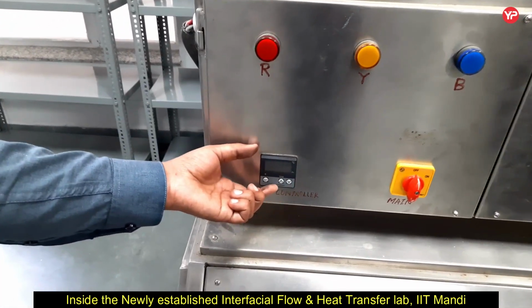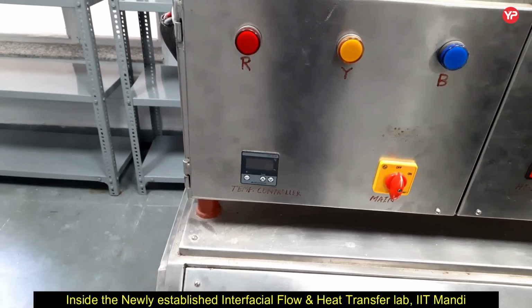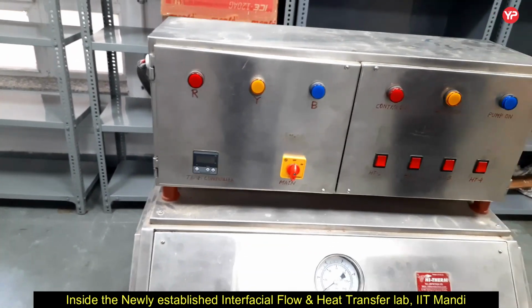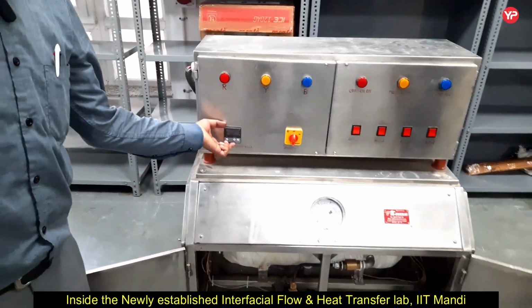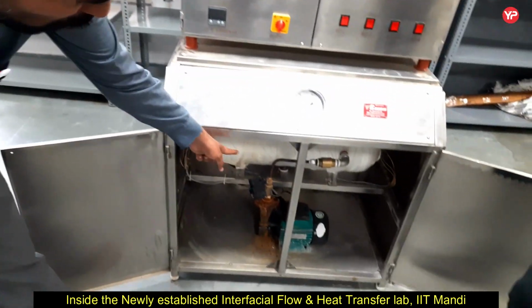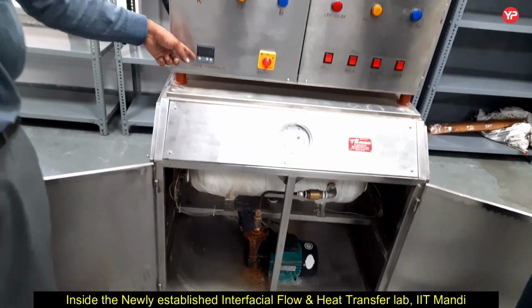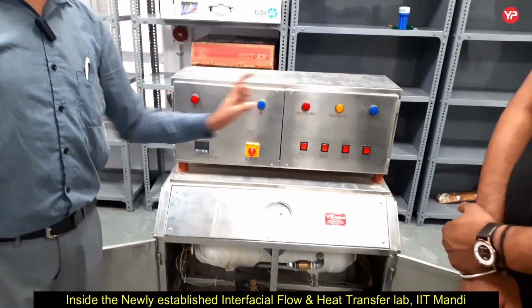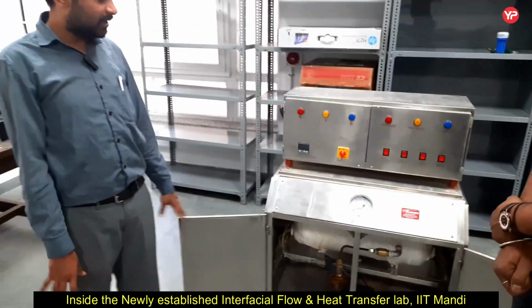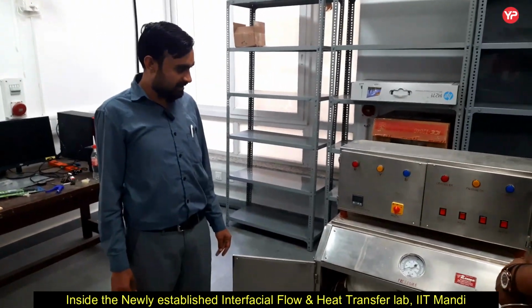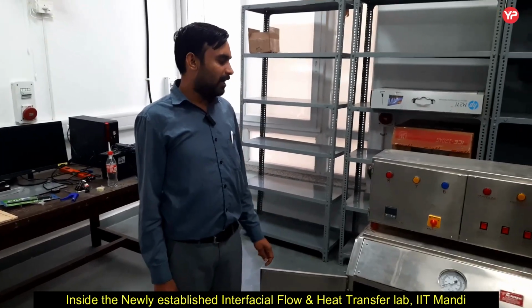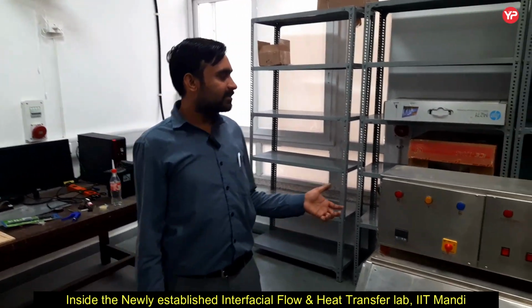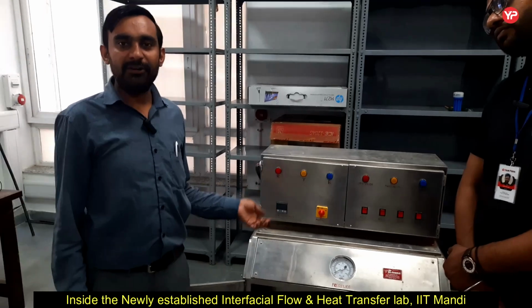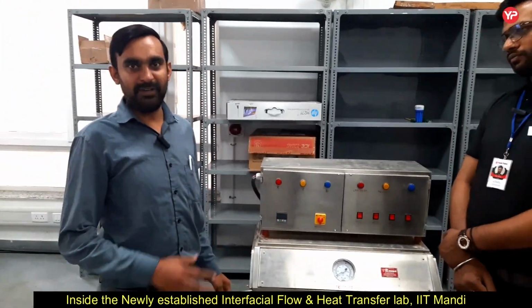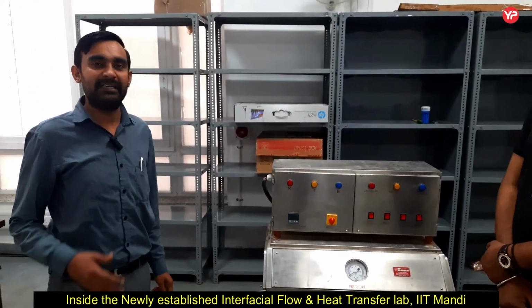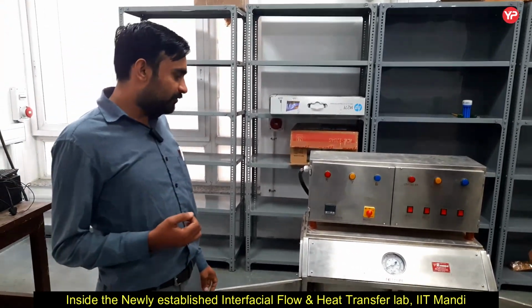Another important point we have over here is the PID controller. This PID controller is another safety feature. Here we set some value of the temperature, and when our boiler drum temperature is greater than the set temperature, it also switches off the heaters. So this has all the safety features in it. This particular non-IBR boiler can provide us steam at a supply mass flow rate of 50 kg per hour. So we can continuously get steam at a maximum rate of 50 kg per hour out of this.